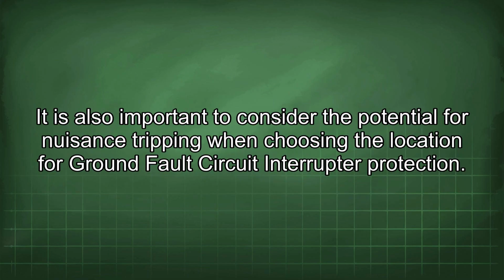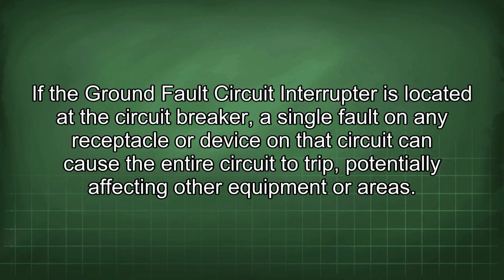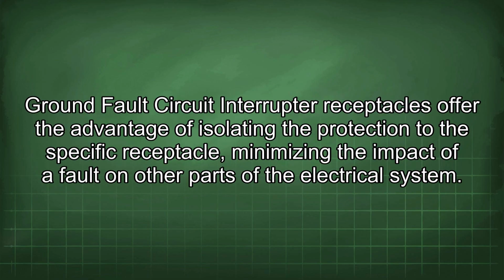It is also important to consider the potential for nuisance tripping when choosing the location for ground fault circuit interrupter protection. If the ground fault circuit interrupter is located at the circuit breaker, a single fault on any receptacle or device on that circuit can cause the entire circuit to trip, potentially affecting other equipment or areas. Ground fault circuit interrupter receptacles offer the advantage of isolating the protection to the specific receptacle, minimizing the impact of a fault on other parts of the electrical system.